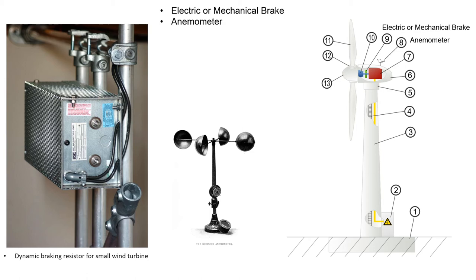On the other hand, a mechanical drum brake or disc brake is used to stop the turbine in emergency situations such as extreme gust events or over-speed wind. This brake is a secondary means to hold the turbine at rest for maintenance, with a rotor lock system as the primary means. Such brakes are usually applied only after blade furling and electromagnetic braking have reduced the turbine speed, as the mechanical brakes can create a fire inside the nacelle if used to stop the turbine from full speed.